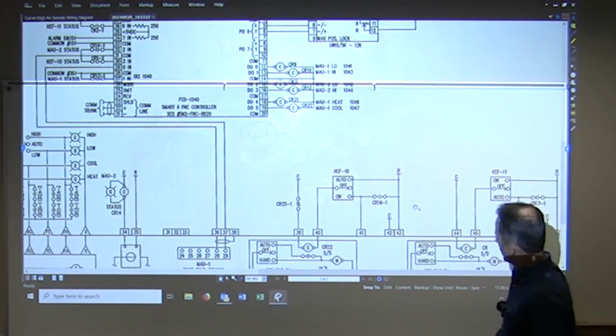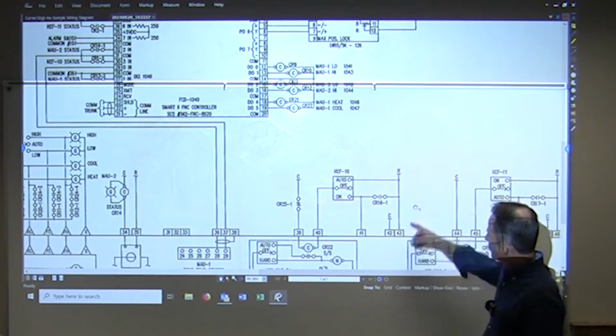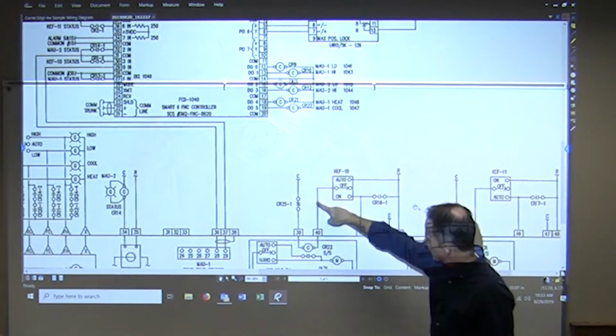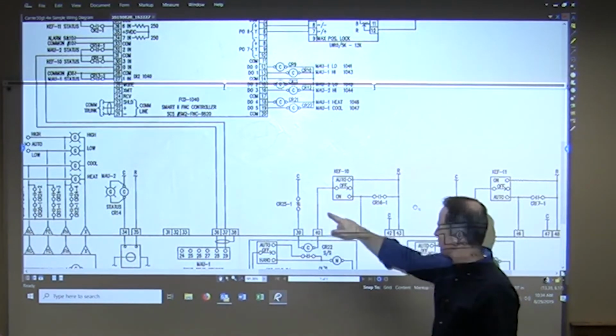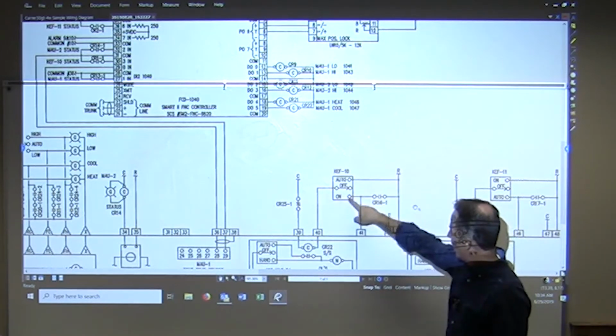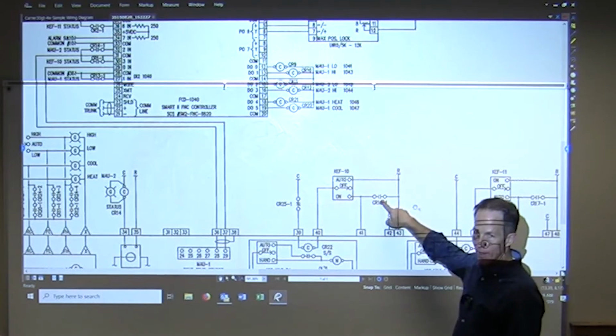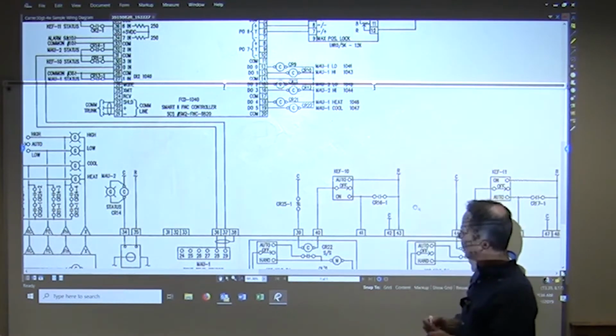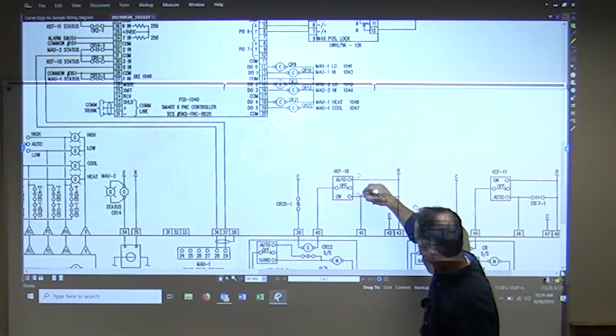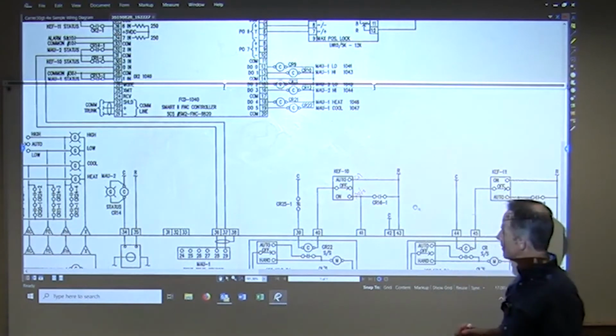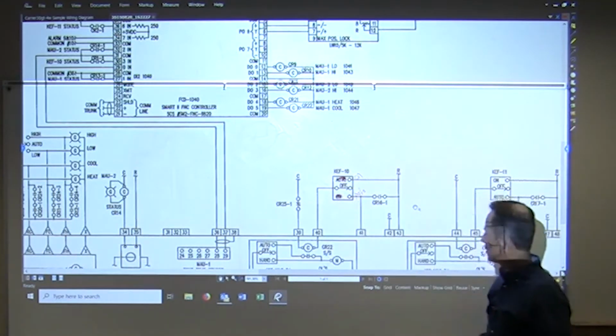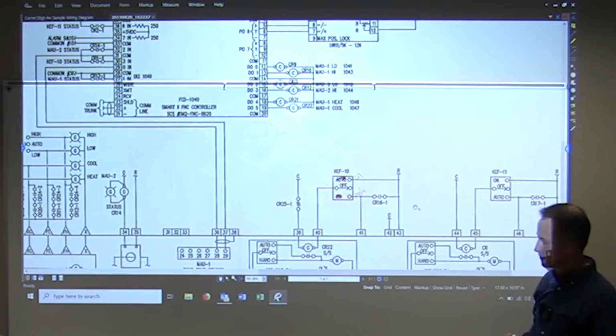Okay, so in auto, R goes over, comes out, energizes, disabled by the safety. In on, you'd have a relay. It's interrupted. So that's more of our auto thing, right? Yeah. So this should be our on, and this should be our auto. Good catch. I didn't see that one before. And see, if you look at it from that perspective, you go back to CR 25-1, where it's on the common. If you put that over here on R, you power R through that, you're bypassing that entire switch right there, right? So you'd be bypassing your handoff on. Yeah. So you gotta keep it on the common, otherwise you're gonna bypass that.